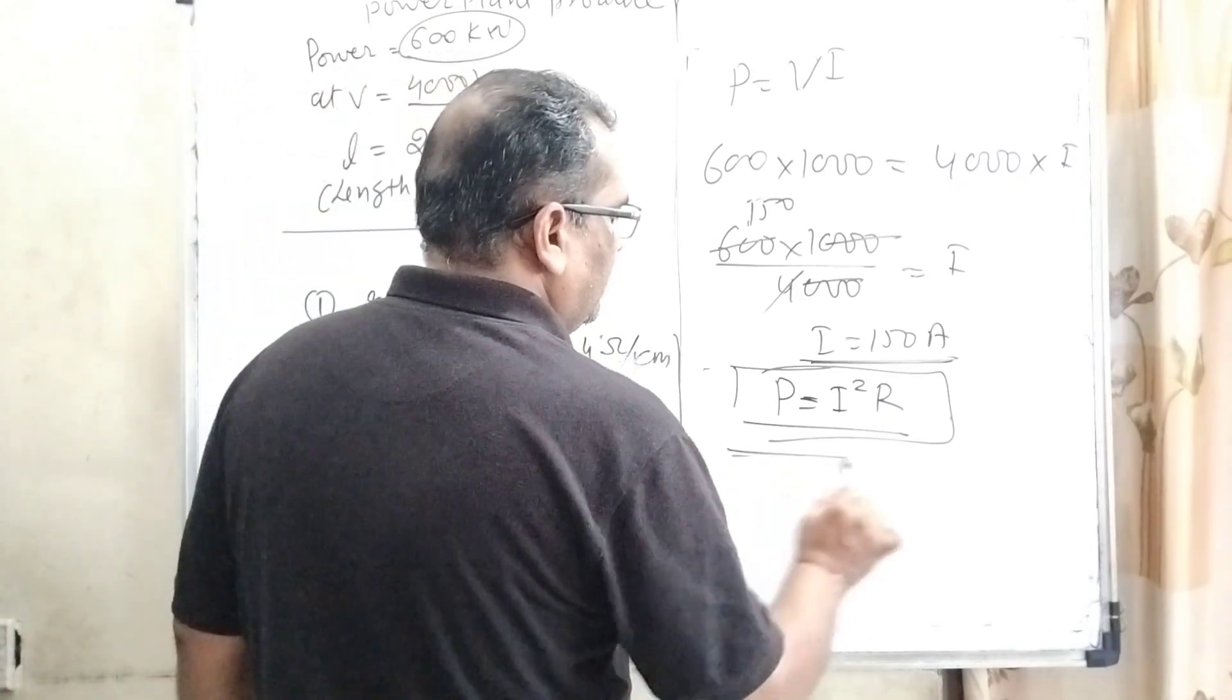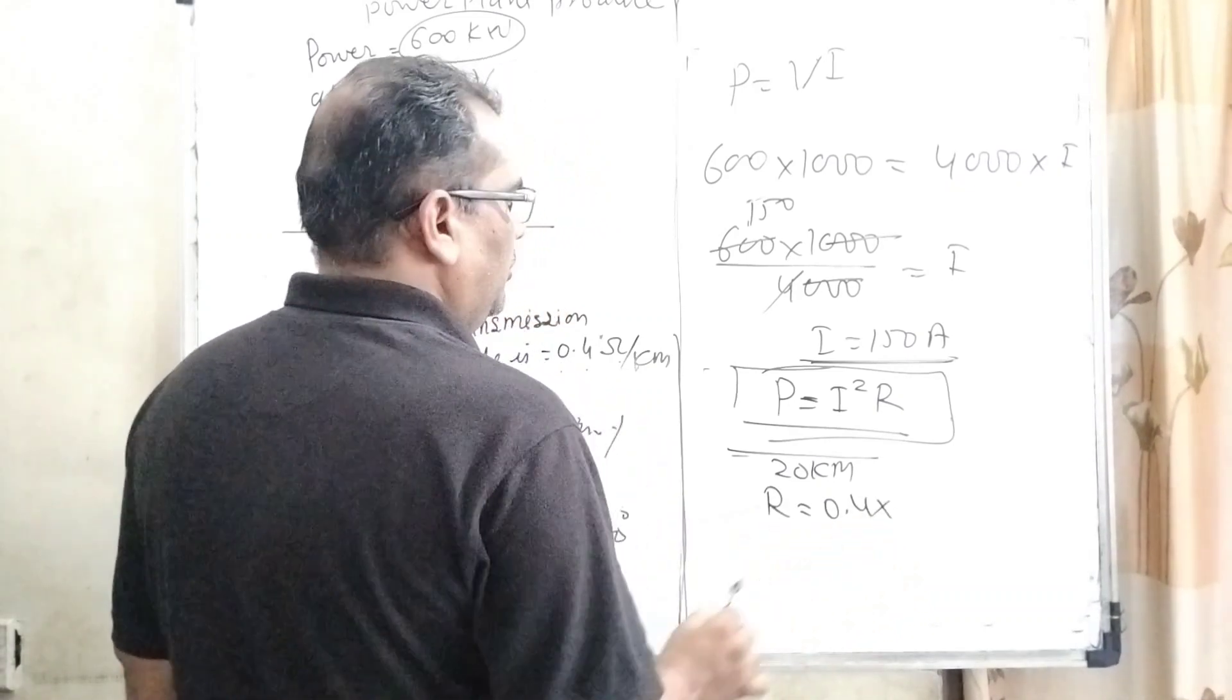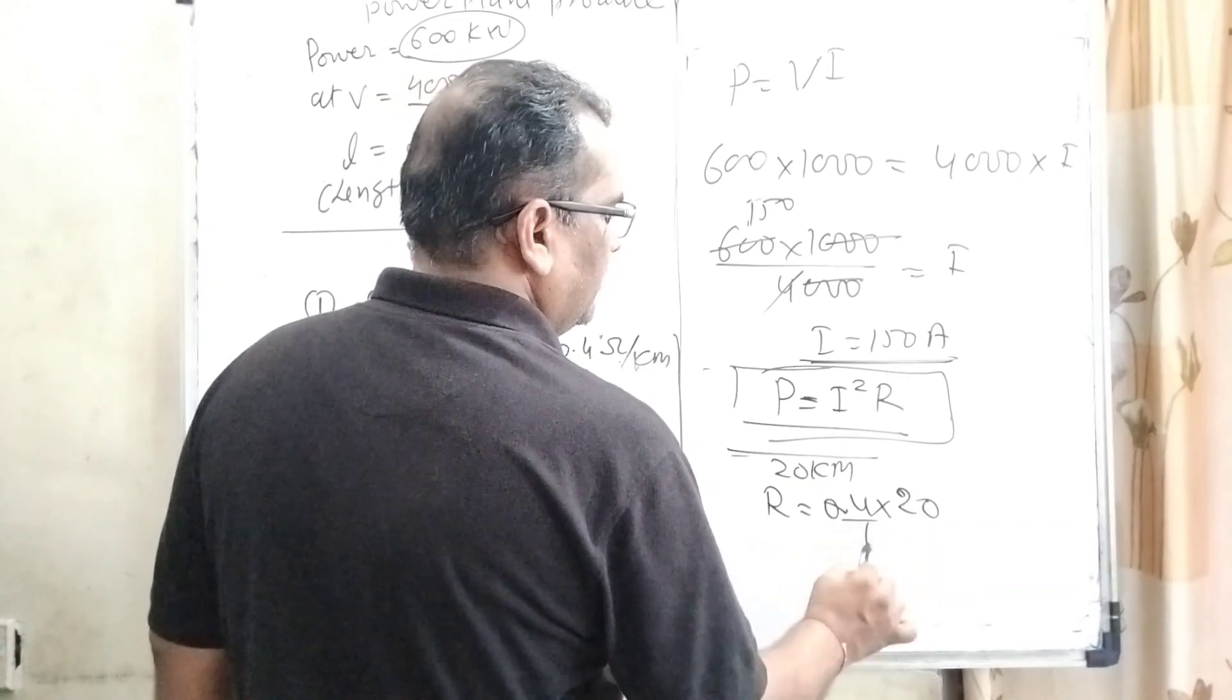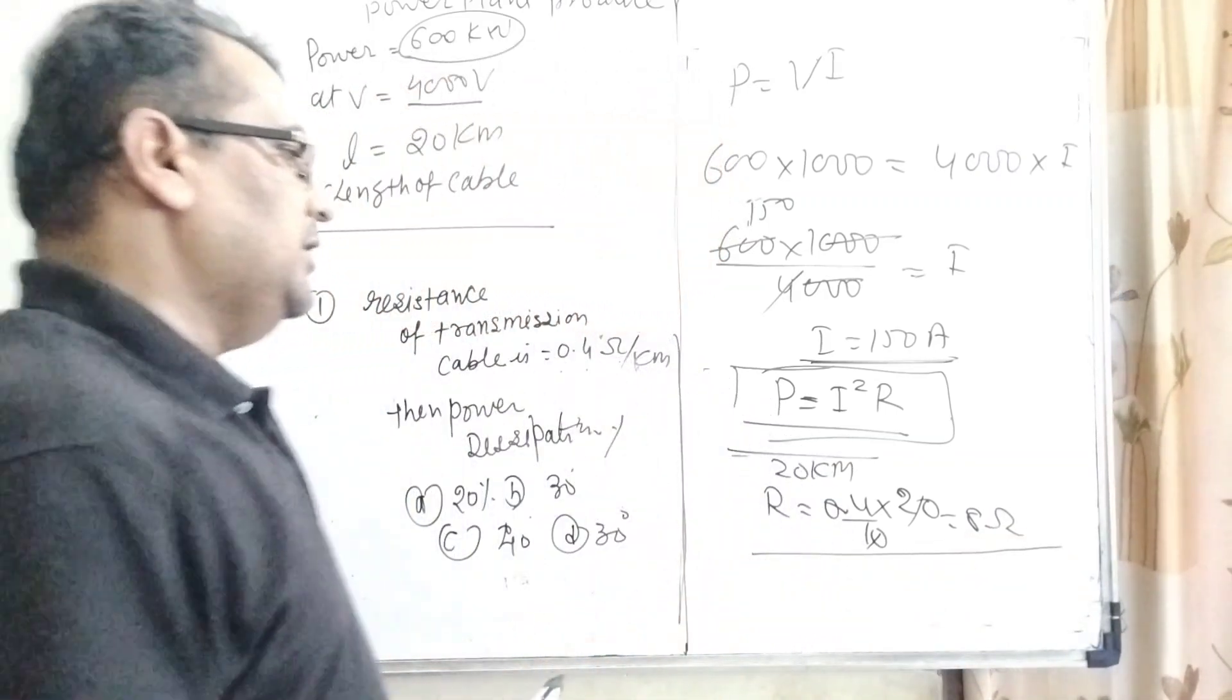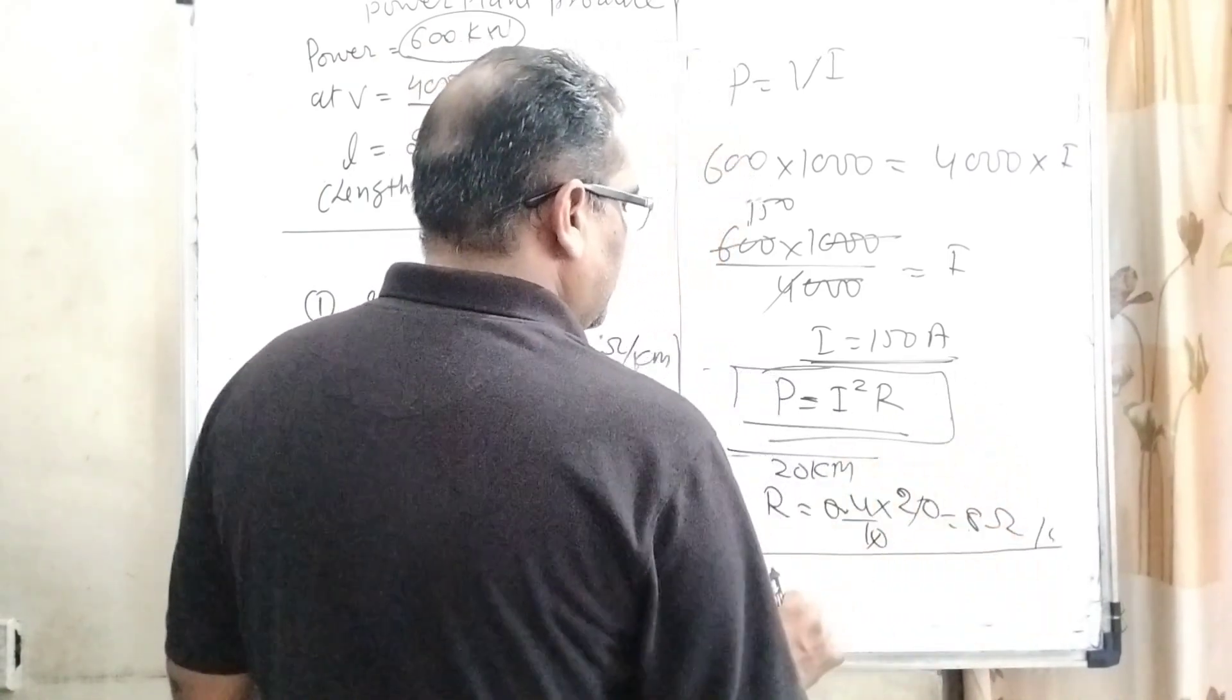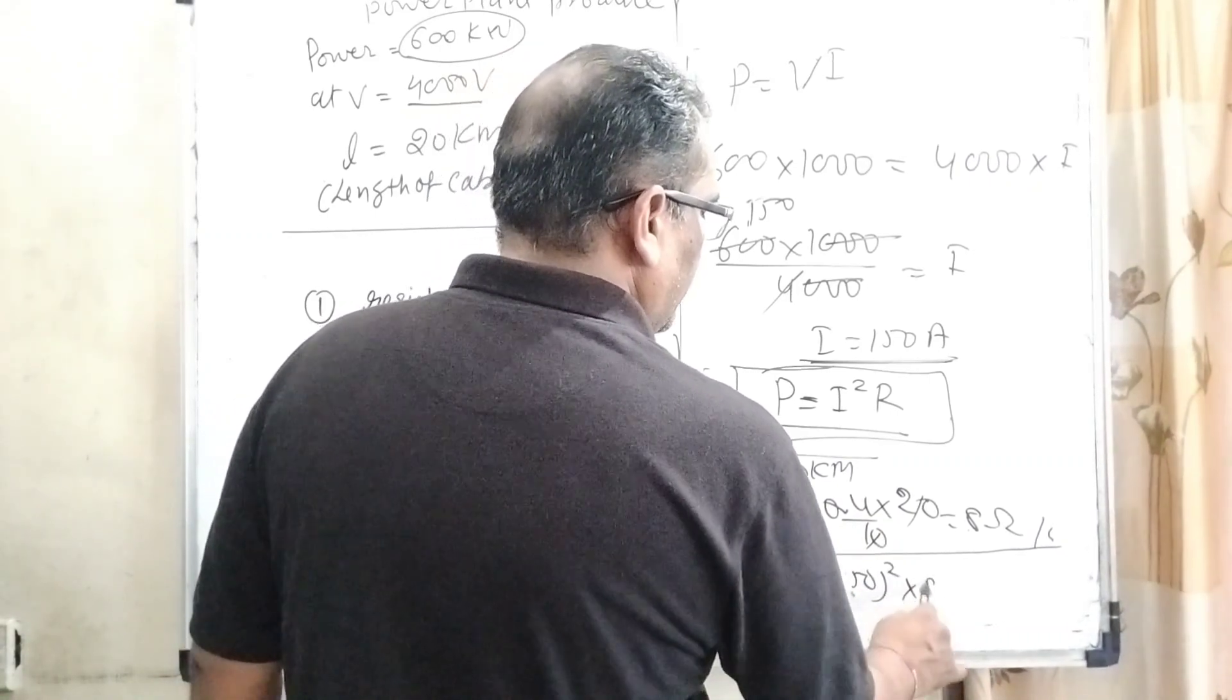Then total length of the cable is given 20 kilometer. So here net resistance 0.4 into 20 kilometer that is 8 ohm. So here we get total resistance R equal to 8 ohm. So now substitute this value here 150 square into 8.